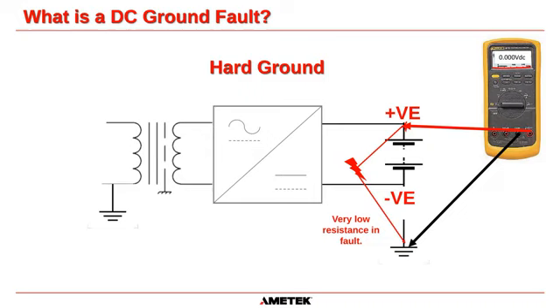Now, bear in mind, this is not detrimental to the system operation. If you get one ground fault on an isolated system that has an isolation transformer, it's not a problem. That's the design of the system. It's only if you get a second ground fault that it would cause a problem. But you should get an alarm when you get one fault, so you can clear it before the other fault becomes apparent and causes issues. So with a positive ground fault, if you measure between positive and ground on a hard ground fault, you should get 0 volts. And if you go between negative and ground on your Fluke, you should see the full system DC voltage, which for most systems that we design, with a 60 cell VRLA battery, is going to be about 135 volts DC.